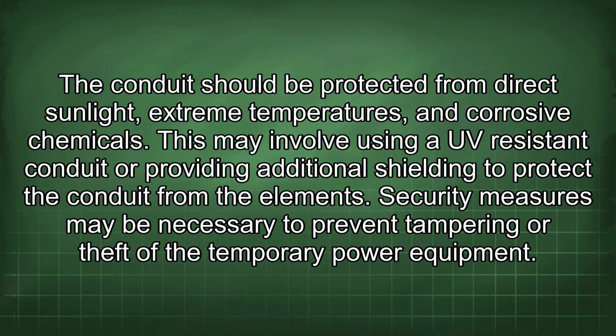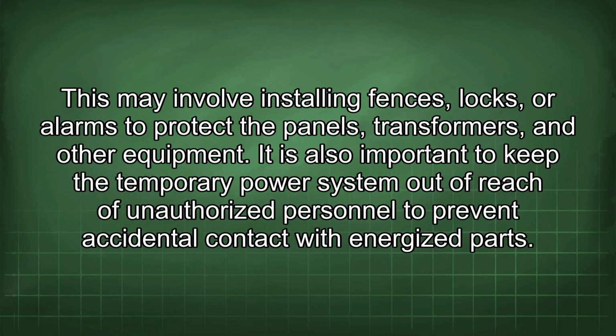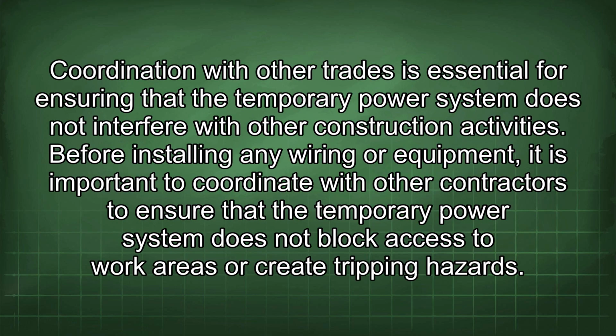Security measures may be necessary to prevent tampering or theft of the temporary power equipment. This may involve installing fences, locks, or alarms to protect the panels, transformers, and other equipment. It is also important to keep the temporary power system out of reach of unauthorized personnel to prevent accidental contact with energized parts.